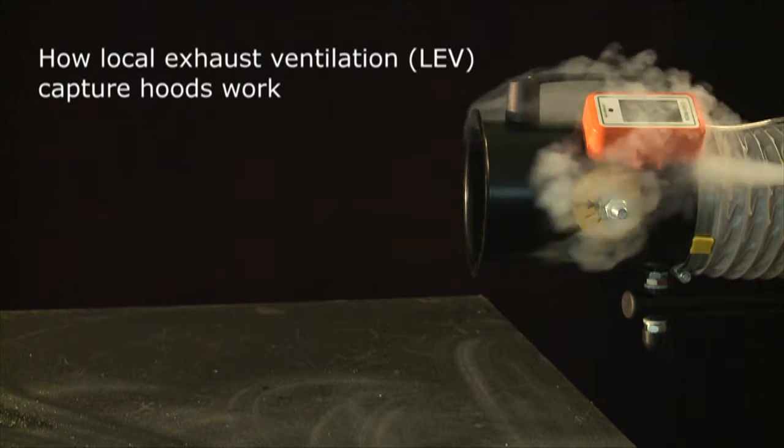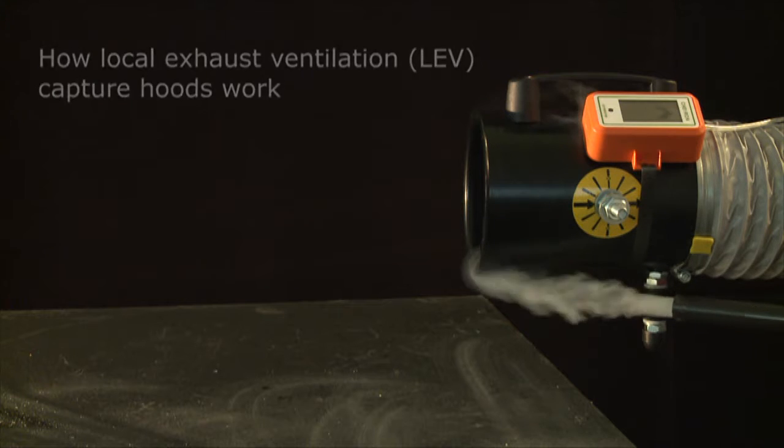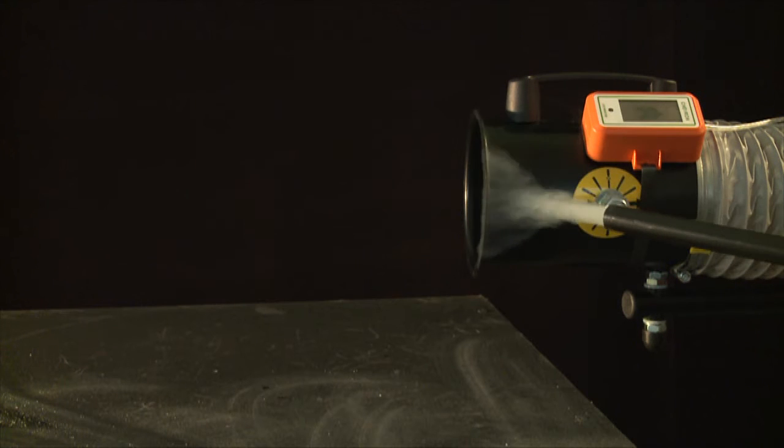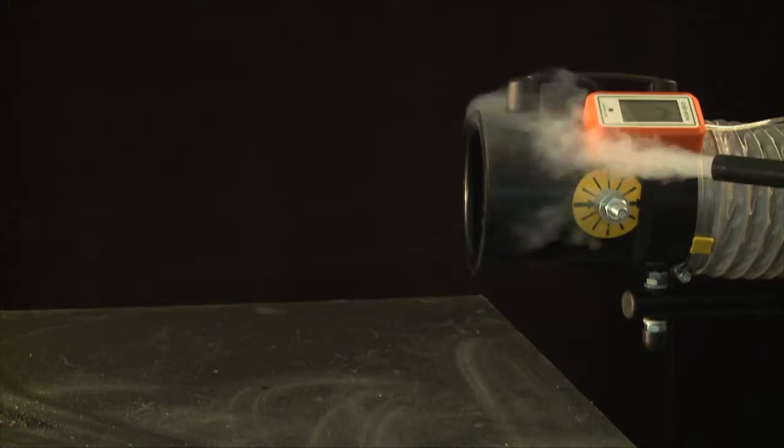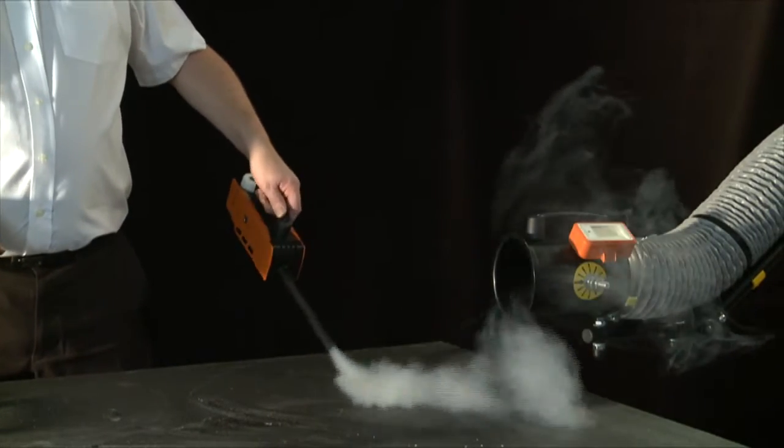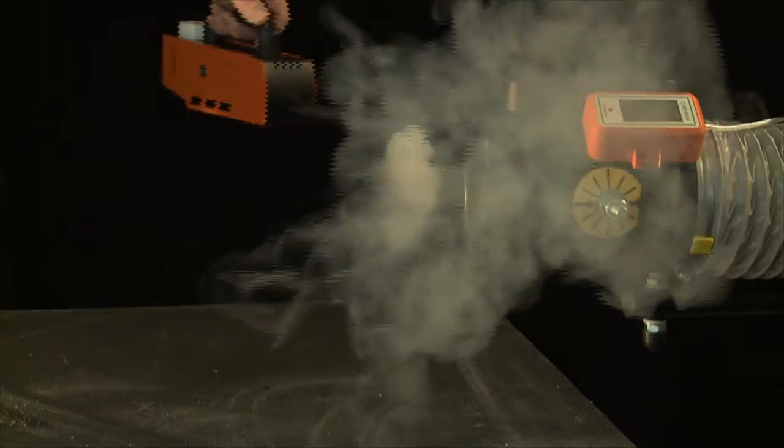Here, we're using an open duct as a capturing hood, and the smoke shows that the airflow contours extend around the back of the hood. With the source at the front of the hood, such airflow is wasted. It has no effect on control.